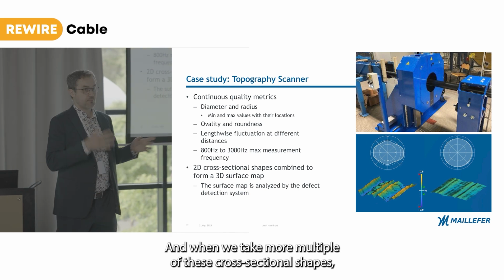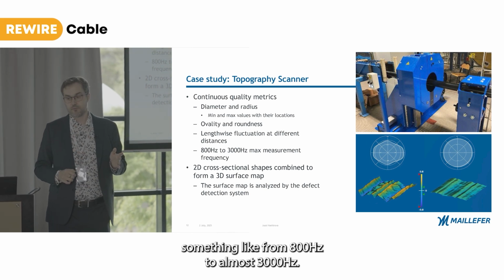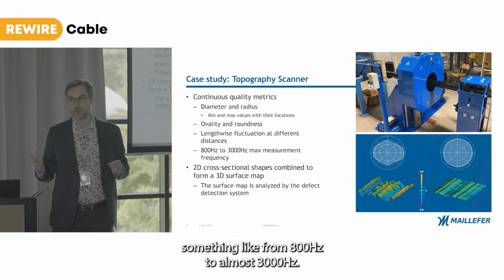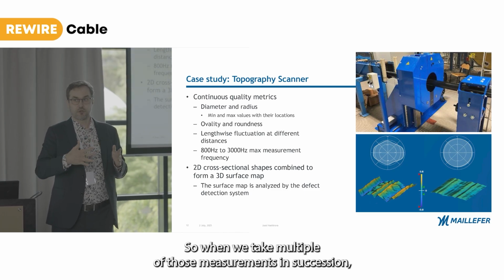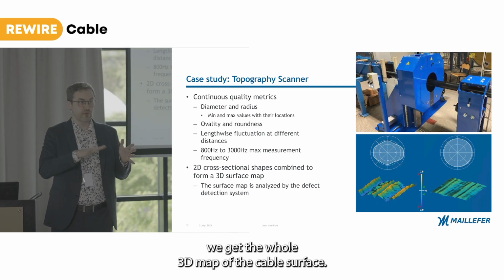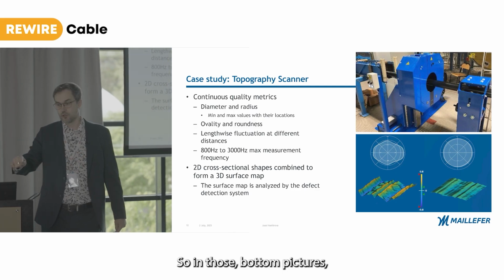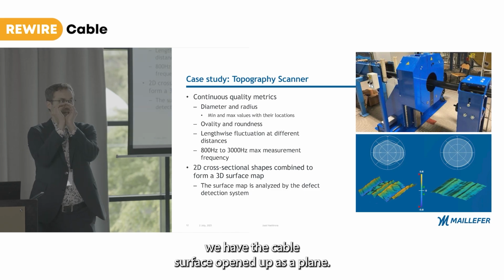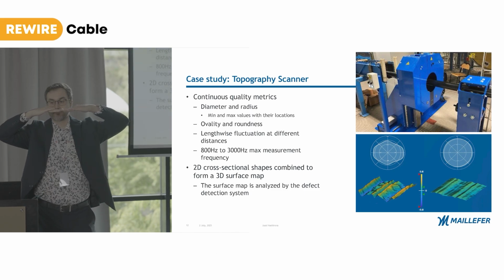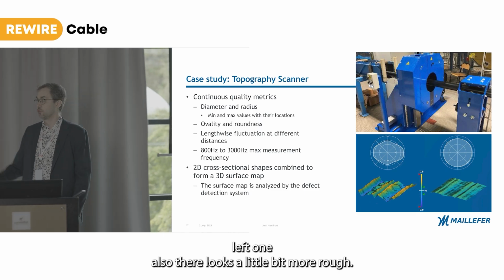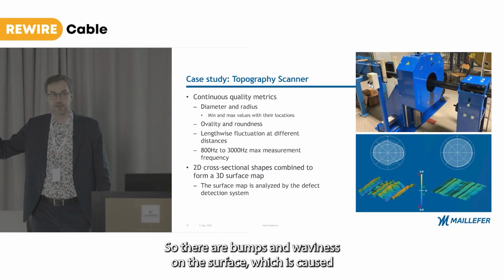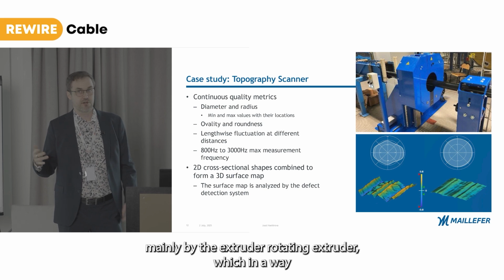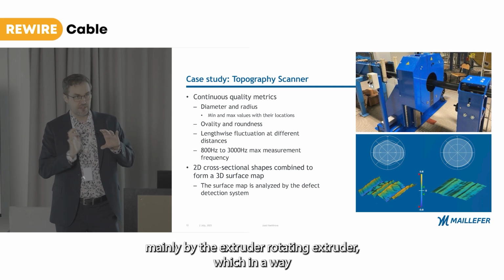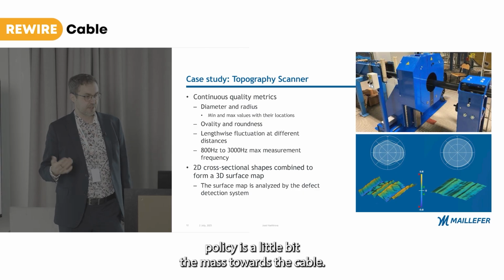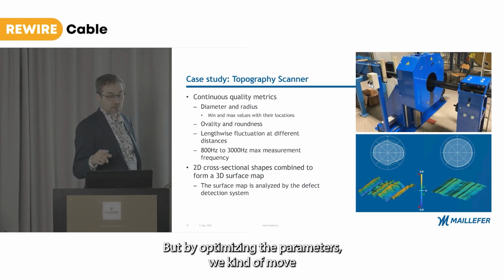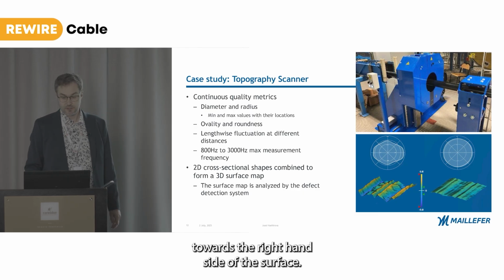When we take multiple of these cross-sectional shapes, something like from 800 Hertz to almost 3000 Hertz in succession, we get the whole 3D map of the cable surface. In those bottom pictures, we have the cable surface opened up as a plane. The left one looks a little more rough, with bumps and waviness on the surface, caused mainly by the rotating extruder, which in a way pulses the mass towards the cable.